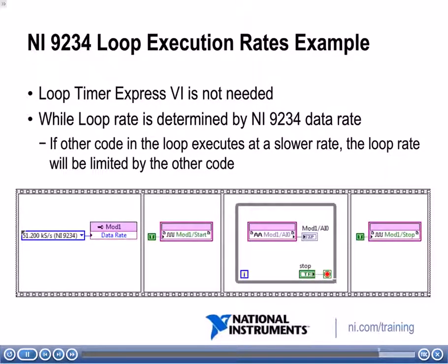One thing to keep in mind: the data rate property sets how often the module will acquire data. However, if the while loop has other code that takes longer to execute, that will slow down the loop rate — the loop rate is being slowed by the other code inside that loop. In this case, we don't have any other code, so the while loop will execute at 51.2 kS per second. Now you can implement loop execution rate using the compact RIO module data rate. Next, we will describe while loop considerations on an FPGA VI.